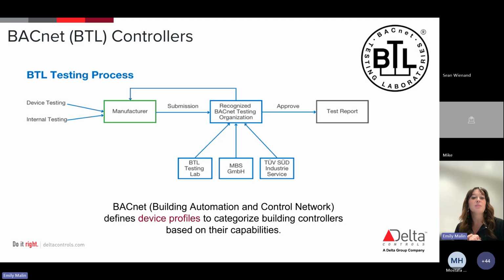And what the BACnet system does is it's defining all of these device profiles, which are going to categorize our controllers based on their capability. And the way that they're doing this is that each one of these device profiles is going to specify a minimum number of BACnet interoperability building blocks. So those are what we all know as BIBBs.